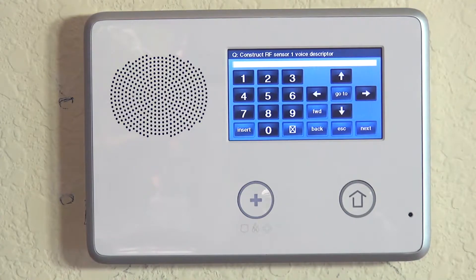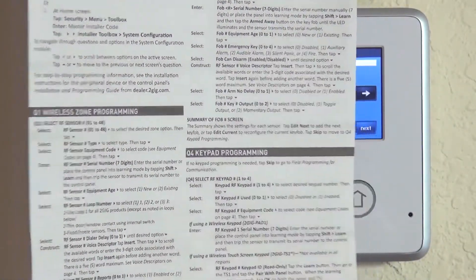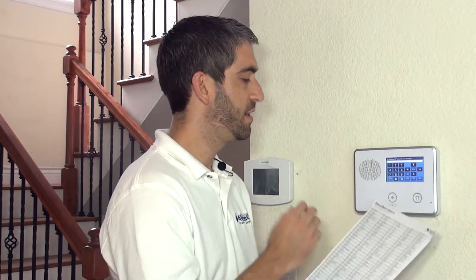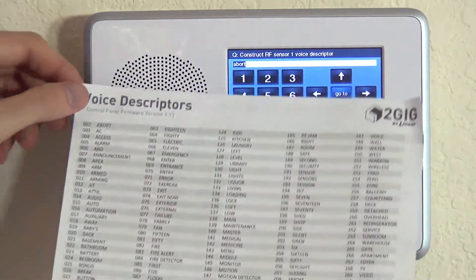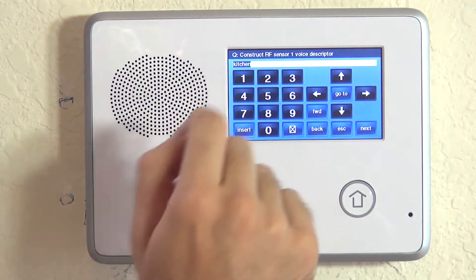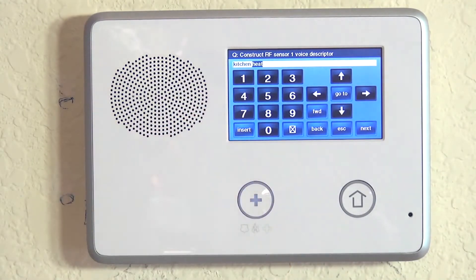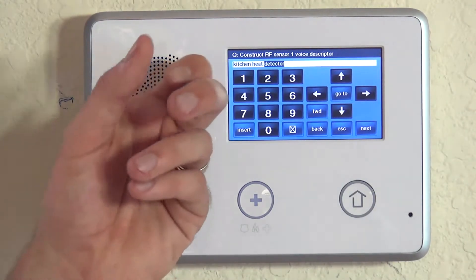We're asked to give voice descriptors to describe what this zone is. Just like with all of our sensor programming, we want to use the chart on the back of our quick programming guide, which comes with our 2GIG GoControl panel. We also have this list on our website, alarmgrid.com. You want to use a three-digit numerical value to equate to a word to describe this zone, and you can use up to five words. We want to call it kitchen heat detector because that's where we're installing it. Kitchen is 125, then we insert heat which is 111, and finally detector is 052 — giving us kitchen heat detector. That's a nice, clear description to let somebody know when there's an alarm exactly what was triggered and where it is.